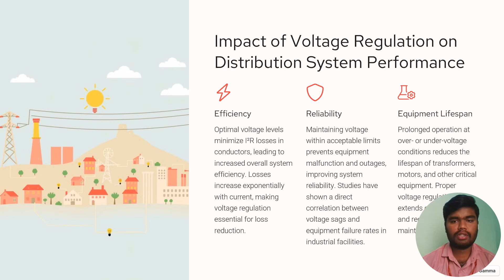Studies have shown a direct correlation between voltage sags and equipment failure rates in industrial facilities. And the last one is equipment lifespan. Prolonged operation at over or under voltage conditions reduces the lifespan of transformers, motors, and other critical equipment. Proper voltage regulation extends equipment life and improves reliability and maintenance. So these three are the impacts of voltage regulation on distribution system performance.